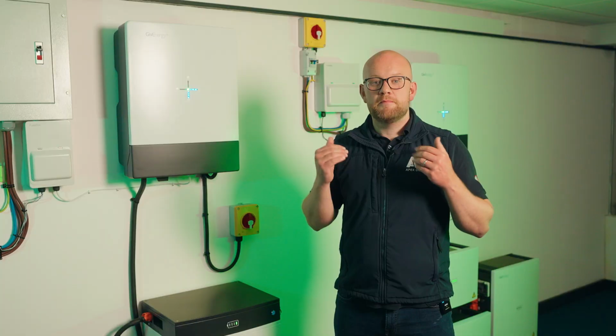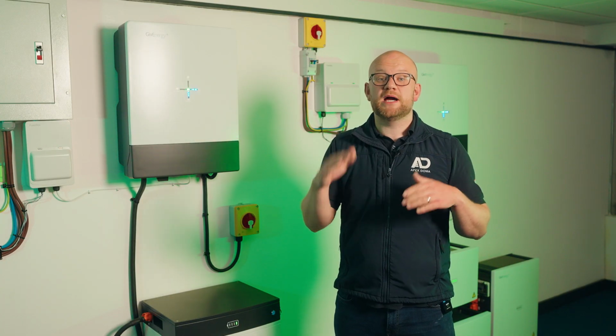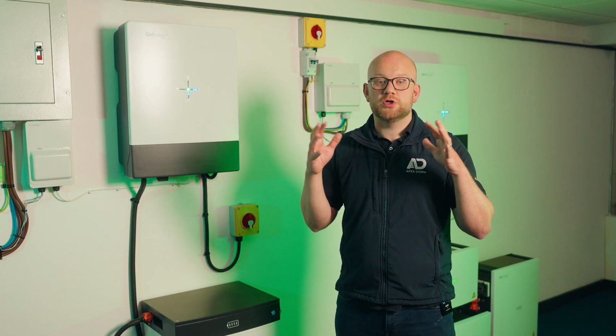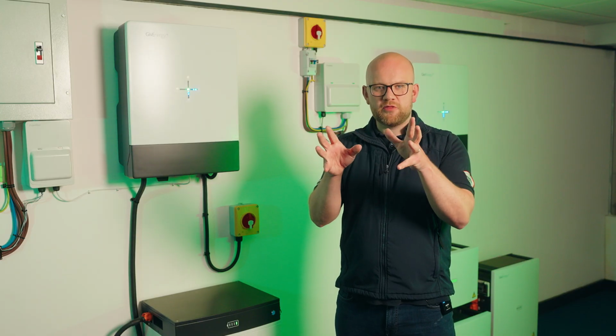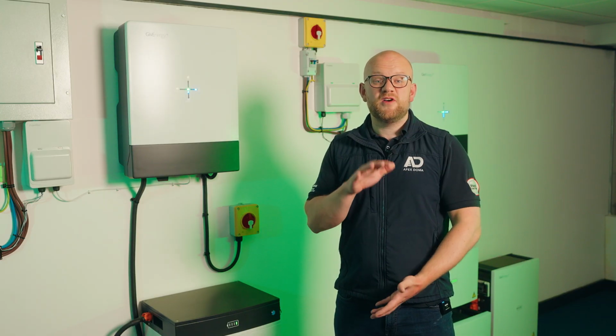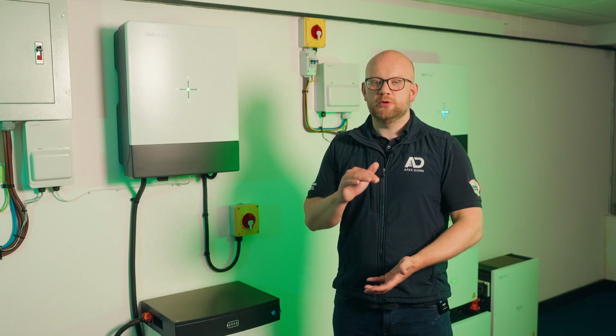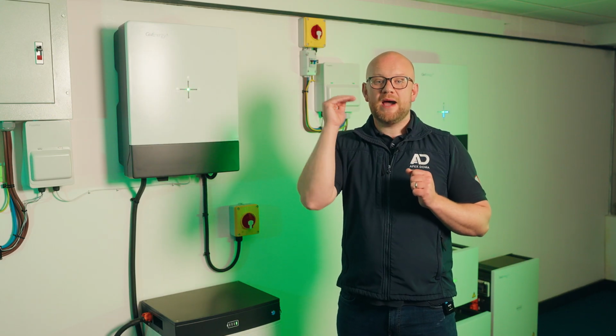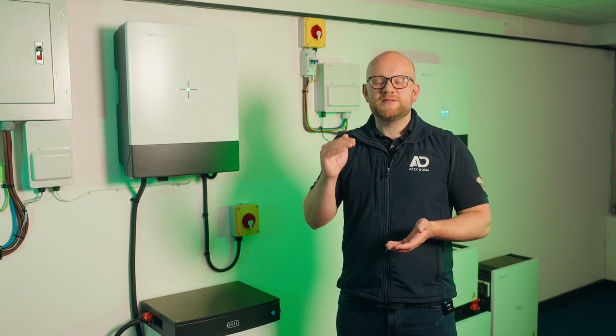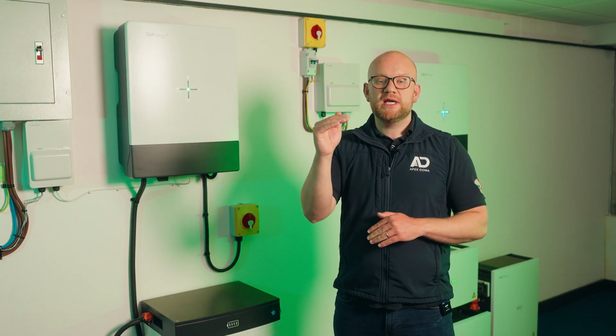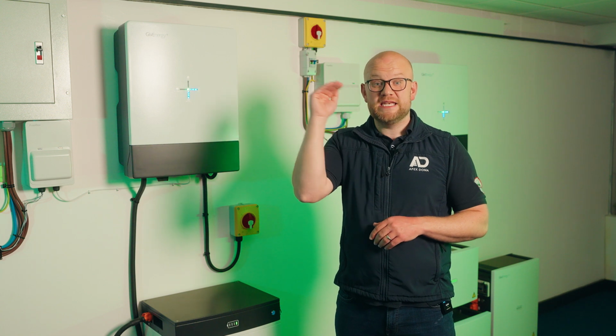So if you have 3 battery packs, you'll essentially get 6.5 kilowatts worth of charge and discharge. Bearing in mind, at this point, you've got 10.2 kilowatt hours worth of storage. So you could effectively fill those battery packs in little under 2 hours. Now, every time you add a battery pack, roughly speaking, you get just over 2 kilowatt hours worth of extra charge and discharge ability. So for 4 battery packs, you get 8.75 kilowatts charge and discharge.